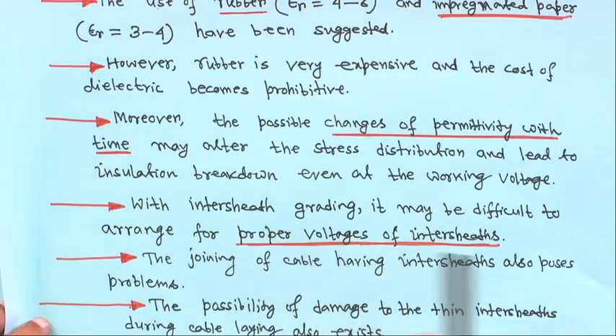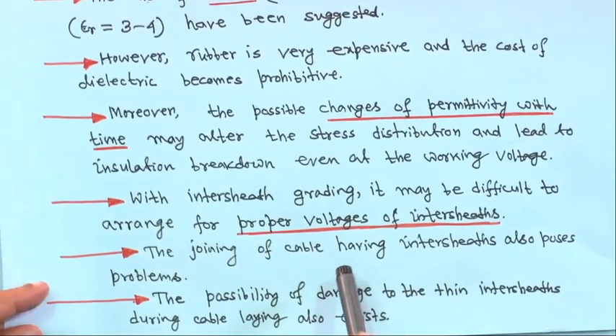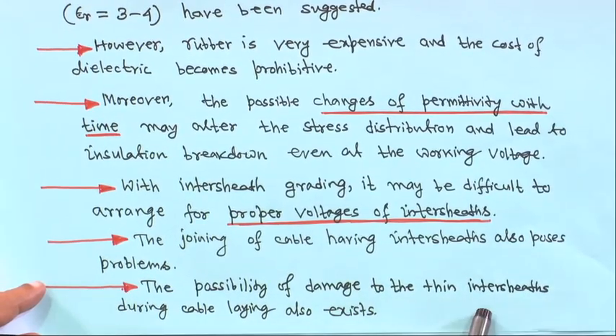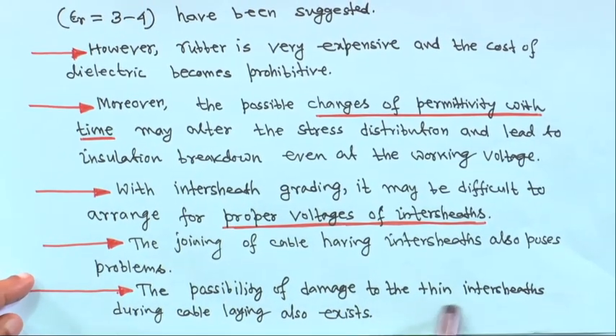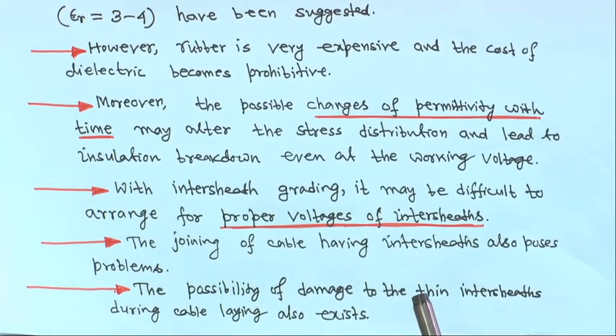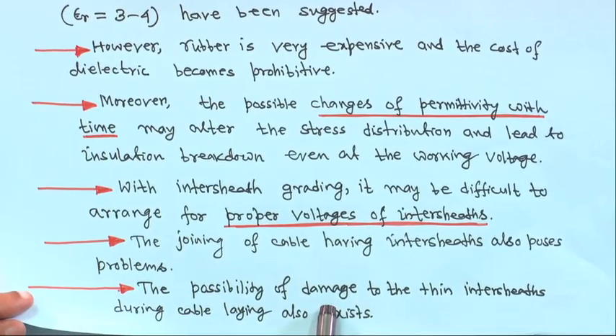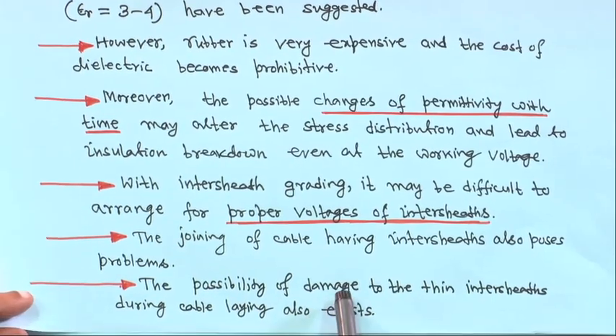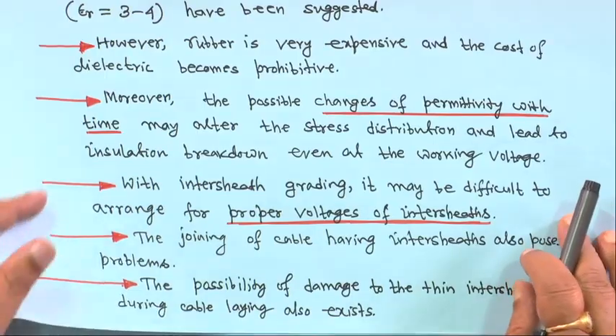The joining of cables having intersheaths also poses problems. If you cut the cable for jointing, the intersheath will be damaged. The possibility of damage to the thin intersheath during cable laying also exists. These are the disadvantages of both capacitance grading and intersheath grading.